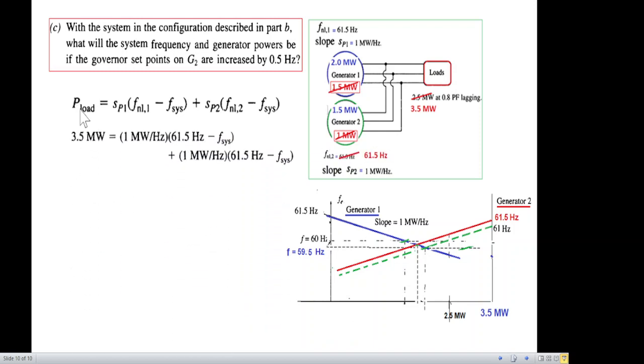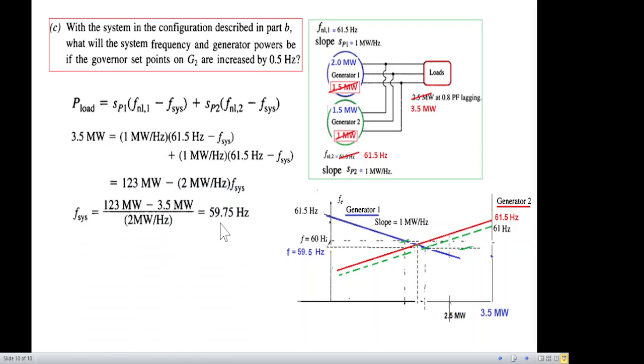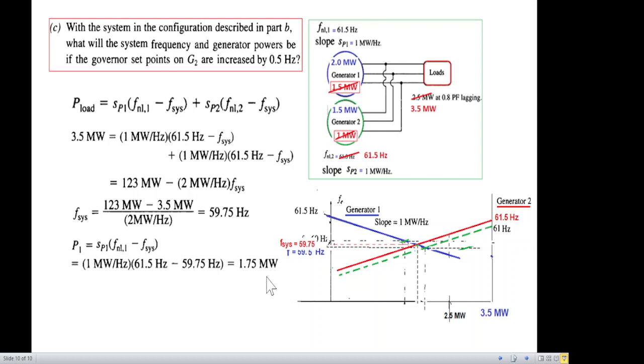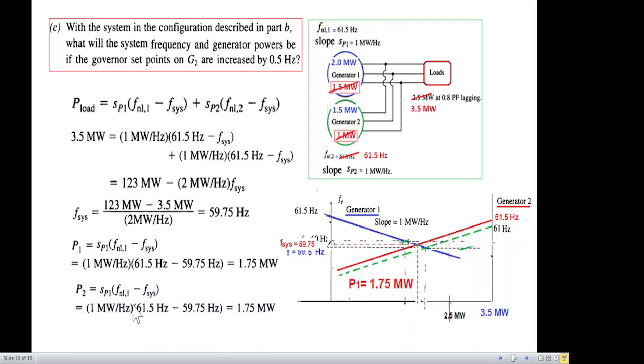With both generator no-load frequencies now at 61.5 Hz and a total load of 3.5 MW, the new system frequency calculates to 59.75 Hz, which is very close to 60 Hz and acceptable. Calculating load sharing: P1 = 1.75 MW and P2 = 1.75 MW, so both generators are now equally sharing the load, which is beneficial — neither is overloaded, which is good for their operational life.